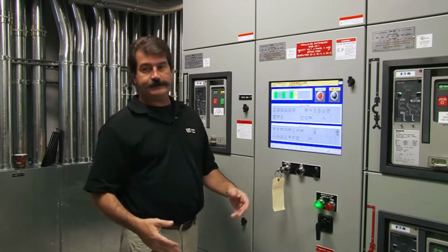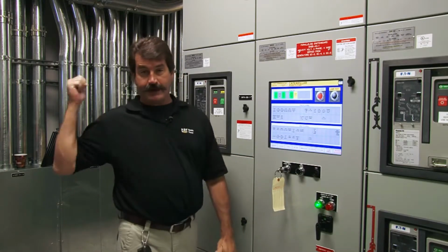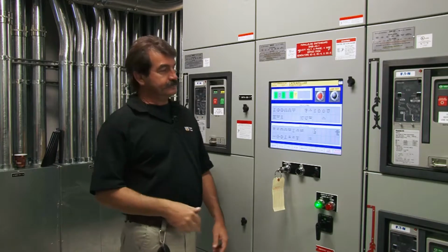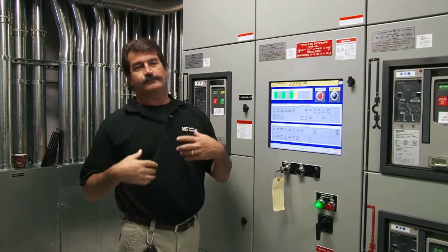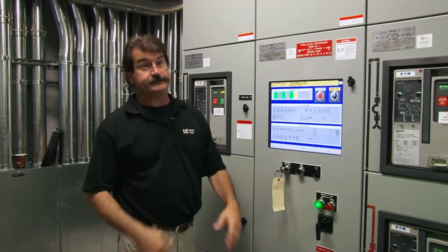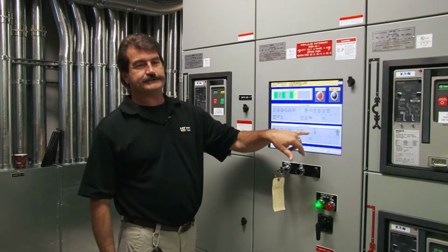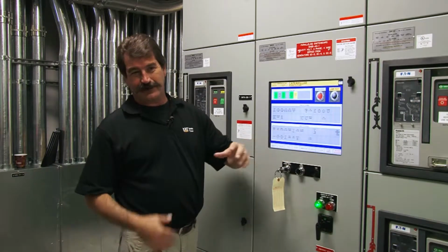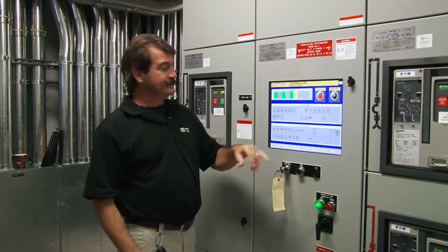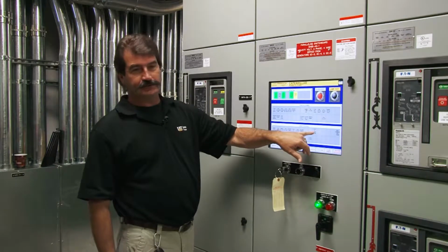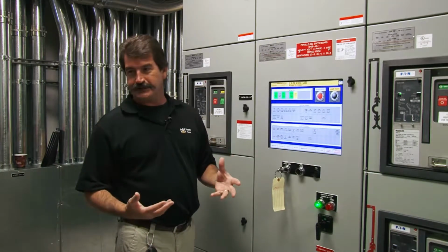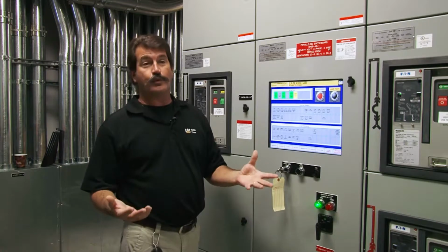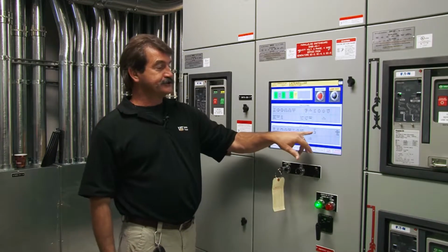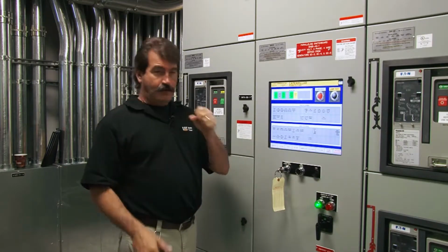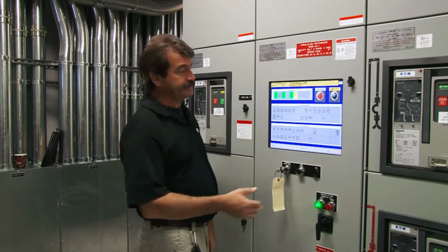Loss of crank terminate. Now it's starting to come from out there. Crank terminate means that you've stopped cranking the gen. What it should say is gen running. That's what crank terminate is, gen running. If you lose that signal, then we've lost the signal that says the gen is running. We don't know what's going on, so we'll shut down the gen if we don't realize whether the gen's running or not.